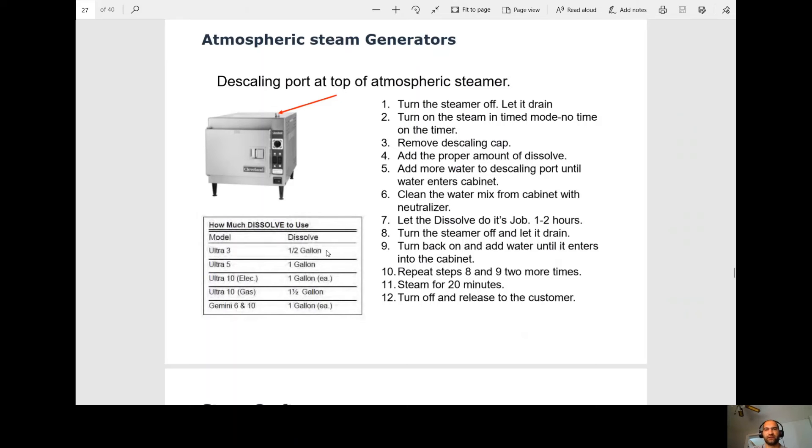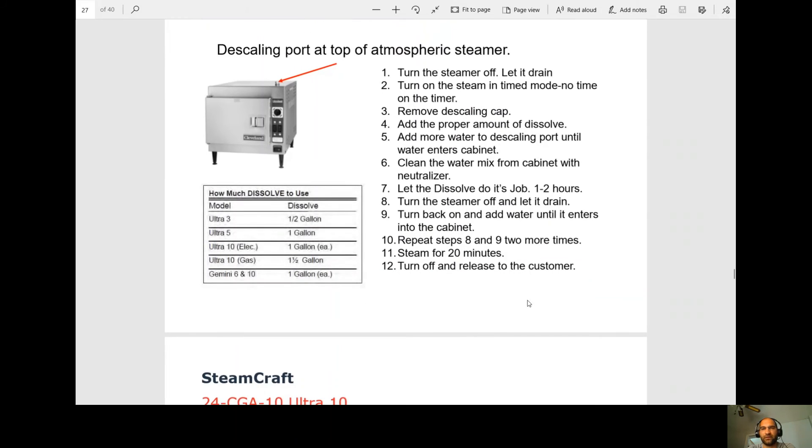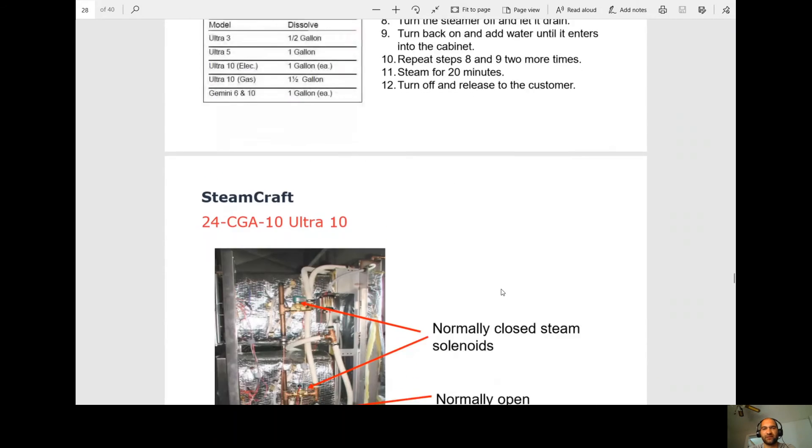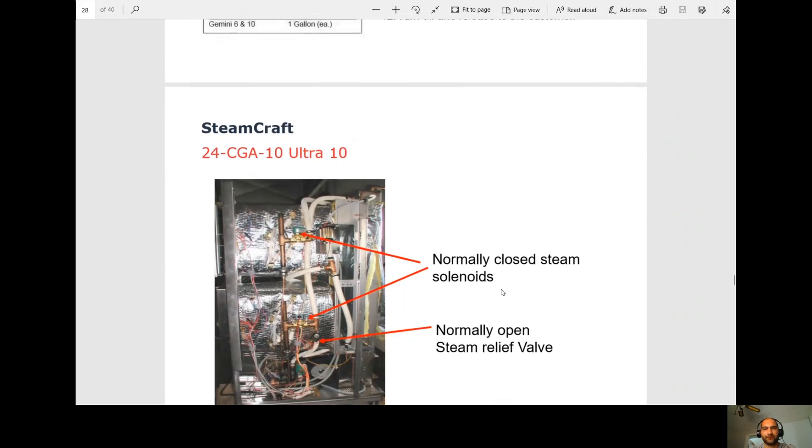Now you want to let it dissolve. So this one we only need one to two hours depending on how badly it's scaled. So some of our customers are every six months. So you could probably get away with the one hour descale if it's being done every six months, but also depending on water hardness and filters and all that good stuff. So now you're going to turn the steamer off. It's going to drain. So it's going to go into a blow down. So you're going to turn it back on and then it's going to fill and you're going to add water one more time through here so that water comes into the cabinet. So we're going to overfill the boiler. We're going to do that two more times. So we're going to drain it, we're going to refill it, we're going to overfill it, and then we're going to steam the unit for 20 minutes. After 20 minutes, the customer can get the steamer back.